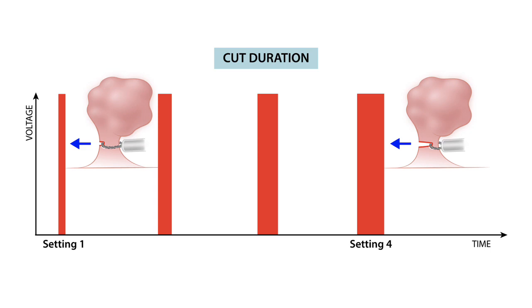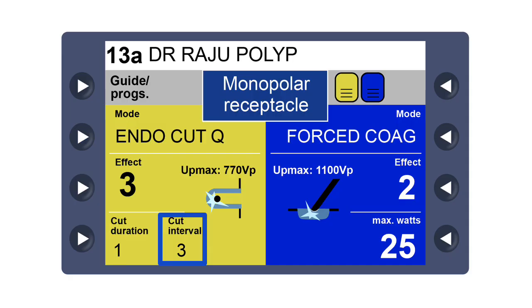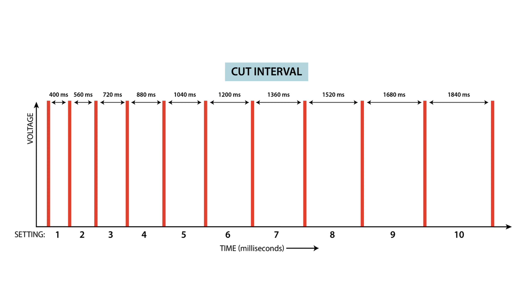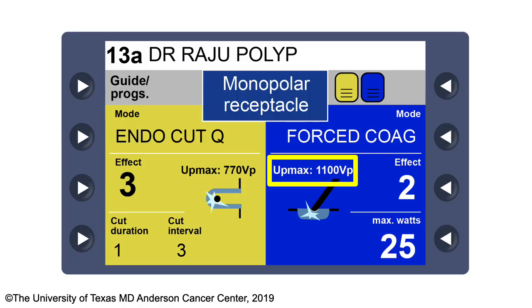Now coming to cut interval. This is the interval between the cuts. As you can see, setting 1 has 400 milliseconds. We typically use 3, that is 720 milliseconds. You can increase the cut interval to 5 or 6 if you want to give more coagulation in between, when you're dealing with a thick pedunculated polyp. So we learned about endocut Q, effect, duration, interval.